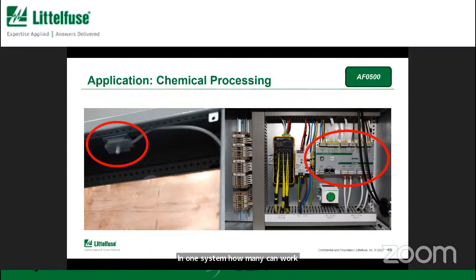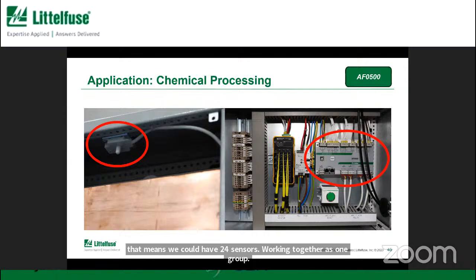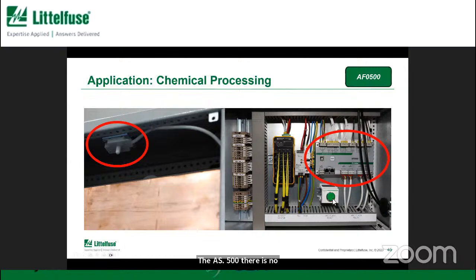That's a good question. With the PGR 8800, we can have 4 relays together, which means we could have 24 sensors working together as one group. With the AF500, there is no limit. You can continue to daisy chain as many relays as needed.